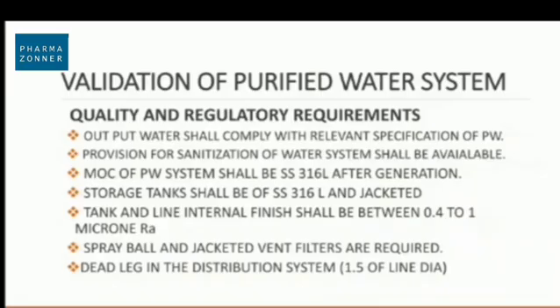The MOC (material of construction) of the purified water system shall be SS 316L. After generation, whatever product-contact or water-contact material is used shall be SS 316L or a highly inert material. The storage tank shall be SS 316L and jacketed, since hot water sanitization is commonly used. The internal line finish shall be between 0.4 to 1 micron Ra. Spray ball and jacketed vent filters are required. Dead legs shall not be present in the distribution system — if more than 1.5D, it is considered a dead leg.